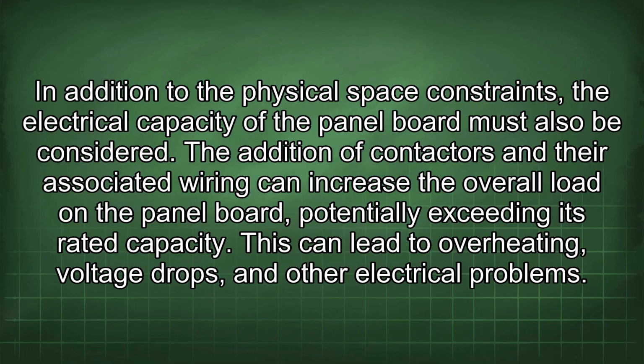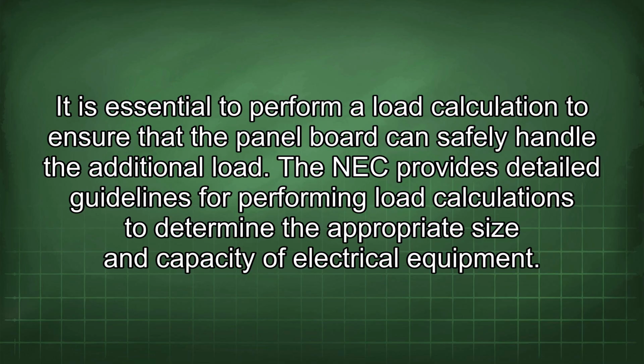In addition to the physical space constraints, the electrical capacity of the panel board must also be considered. The addition of contactors and their associated wiring can increase the overall load on the panel board, potentially exceeding its rated capacity. This can lead to overheating, voltage drops, and other electrical problems. It is essential to perform a load calculation to ensure that the panel board can safely handle the additional load. The NEC provides detailed guidelines for performing load calculations to determine the appropriate size and capacity of electrical equipment.